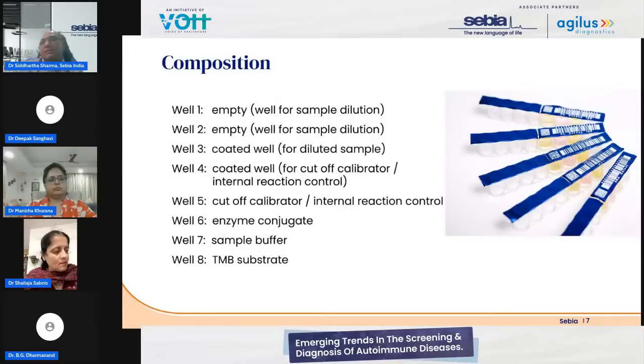Whereas in this particular system, if there is improper storage or a deficiency in the storage conditions that leads to deterioration of reagents, it will lead to deterioration of the control itself. So the test will not proceed further. That will stop the generation of an inaccurate test result, so the result will not be generated, which definitely prevents a wrong report from being generated by any laboratory.